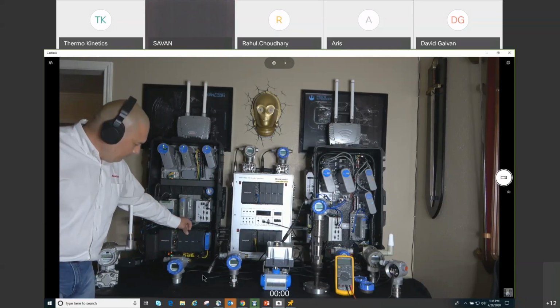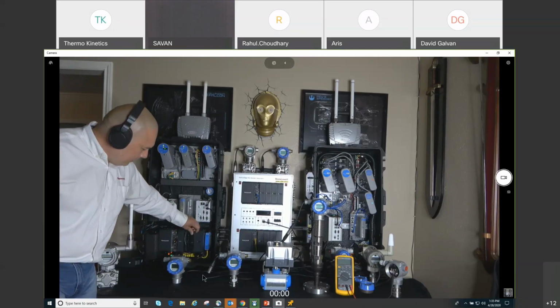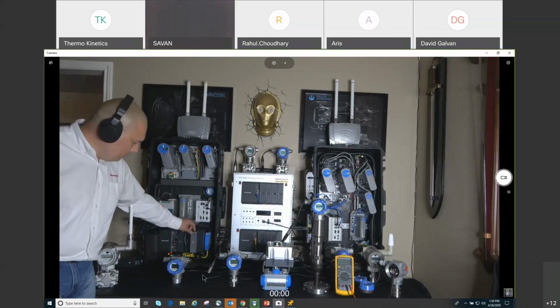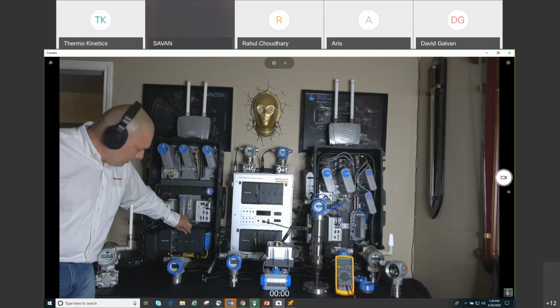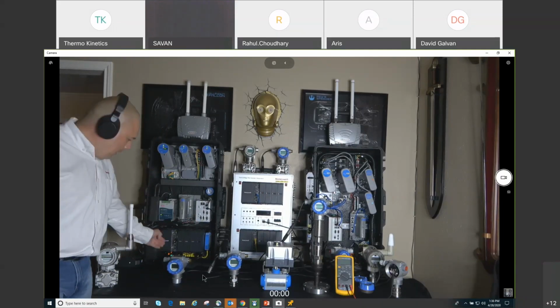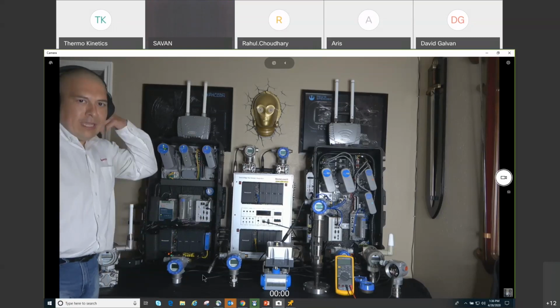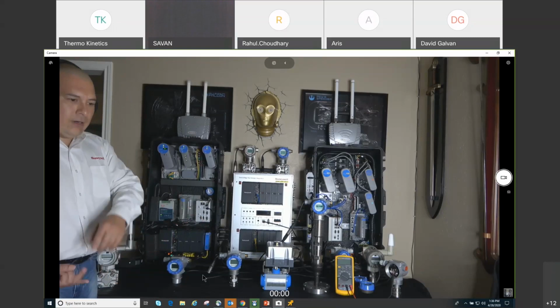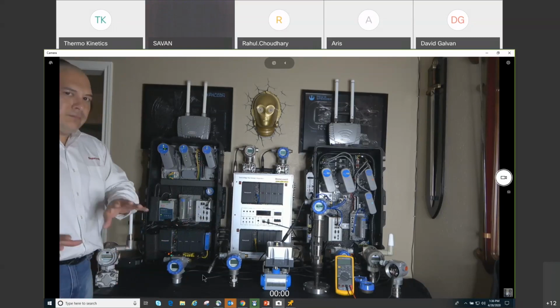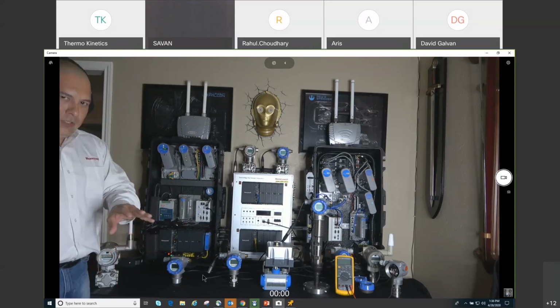And then our doors here, we have a full swing door that I can completely move out of the way when I'm working on the PLC. I can remove that door and completely move it out of the way, and get to my terminals the way I need to. What you see here is a simplex system: 1 power supply, 1 CPM, a 4-slot chassis rack with universal I/O cards. Now we do have static cards: DI cards, DO cards, 120 volt 240 cards, pulse in-pull cards. We have all the purpose-built cards. But if you want universal I/O, we have that, and that's what you see here today.